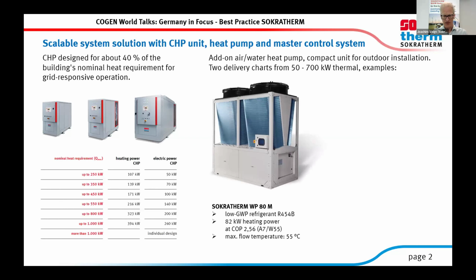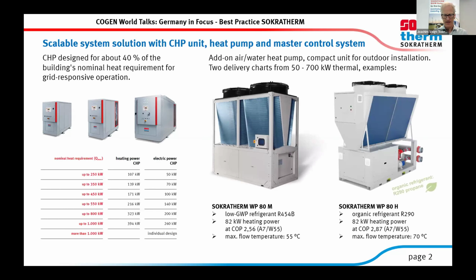One comes with a conventional refrigerant for flow temperatures up to 55 degrees. Just an example here with an 80 kilowatt heating power with a COP of a bit more than 2.5. And the alternative is a heat pump series with an organic refrigerant, with propane as a refrigerant. At the same heating power, the COP is slightly higher, close to 3. And the possible flow temperatures also are higher, up to 70 degrees. So this is what can be chosen from.